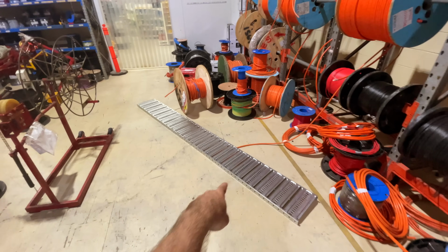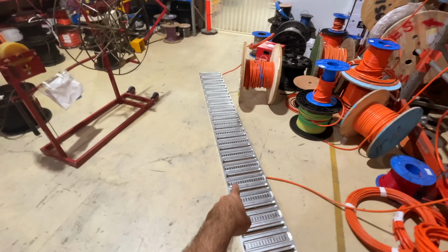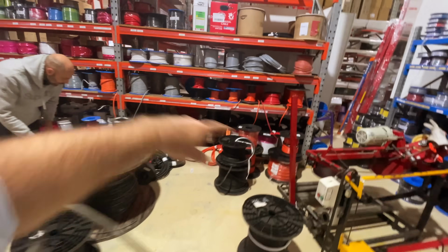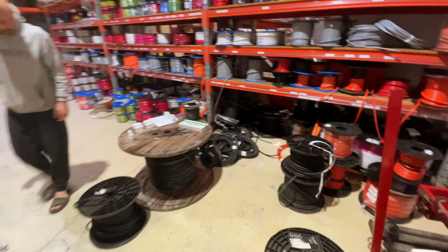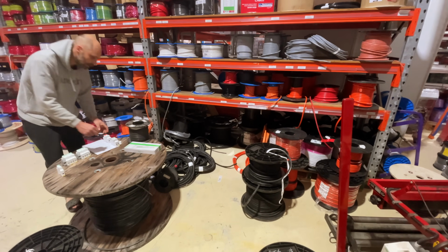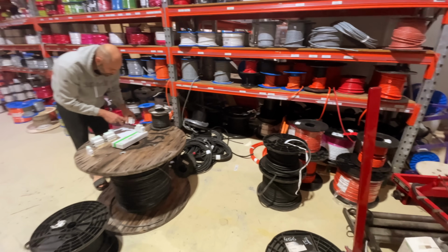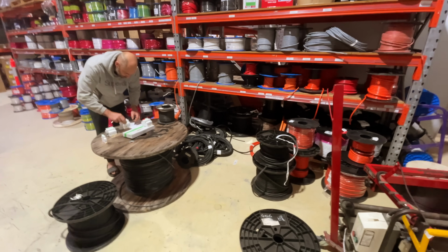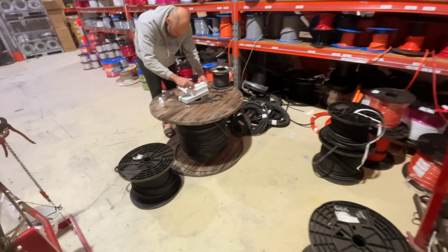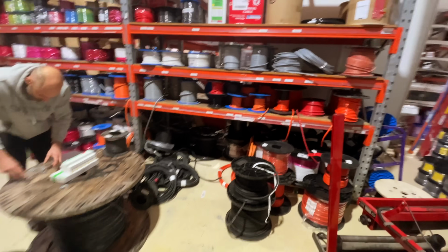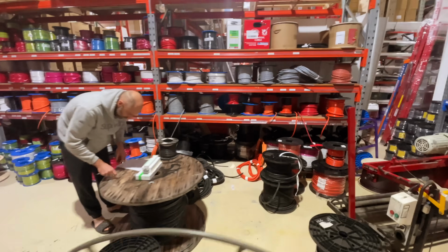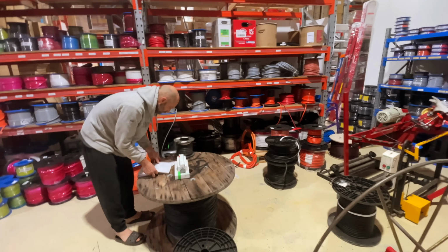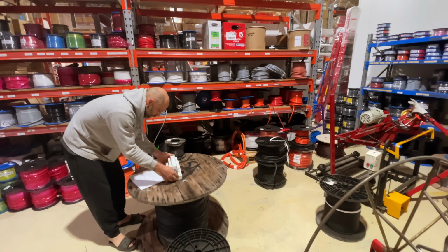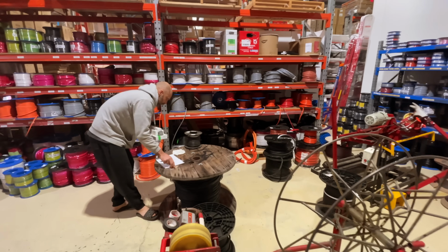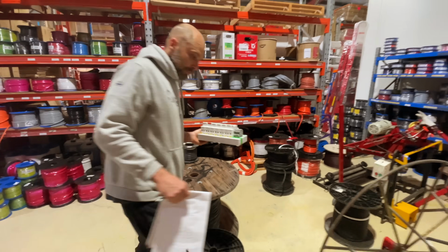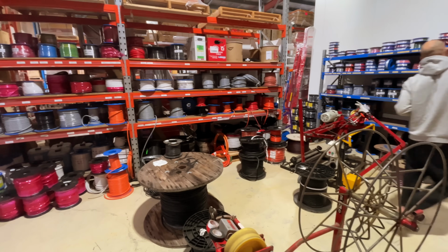At the electrical wholesalers we picked up some 300mm cable tray. Dee's gone through and figured out the cables. We don't have 10mm 3-core, so ideally we'd want that, but what we found is a big roll of 4-core and earth - 5 cores of 6mm tinned flex. We're going to pair 2 together so we've got roughly the same square area, all in one package, so we can send that down to the engine room.